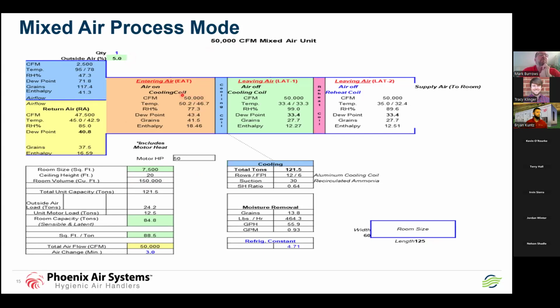Okay, of that, 5% of that air comes from the outside. This happens to be 95 dry bulb, 78 wet bulb. We can talk about the RH and dew points, not a big deal for this discussion. What is a big deal is the return air. So if I have 50,000 CFM of total CFM and 5% outside air, that means I'm bringing back 47,500 back to the unit.